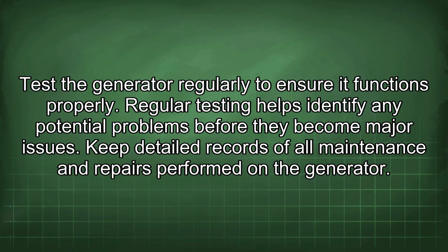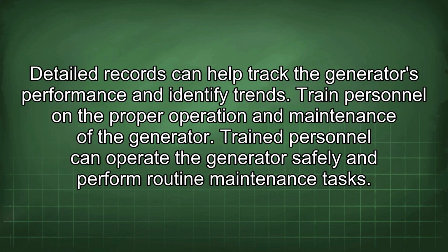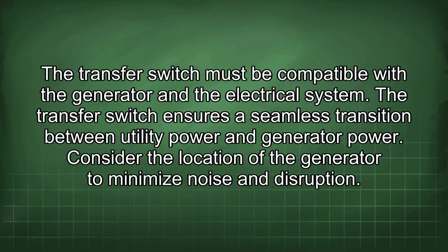Keep detailed records of all maintenance and repairs performed on the generator. Detailed records can help track the generator's performance and identify trends. Train personnel on the proper operation and maintenance of the generator. Trained personnel can operate the generator safely and perform routine maintenance tasks. The transfer switch must be compatible with the generator and the electrical system. The transfer switch ensures a seamless transition between utility power and generator power.